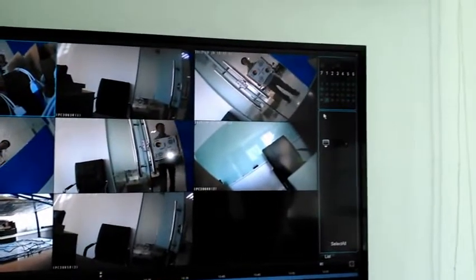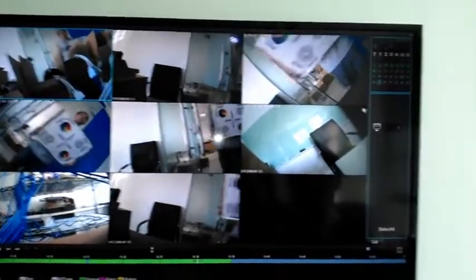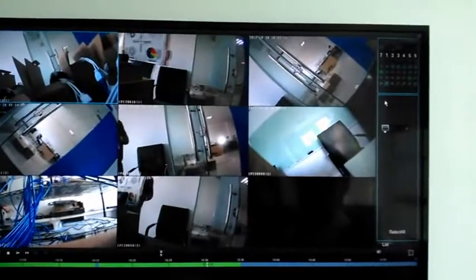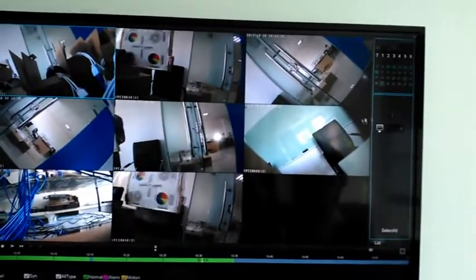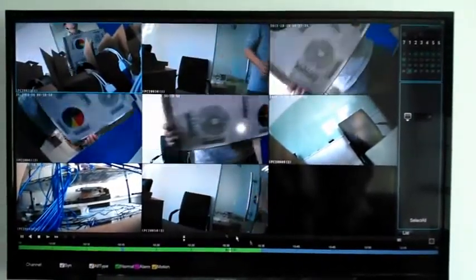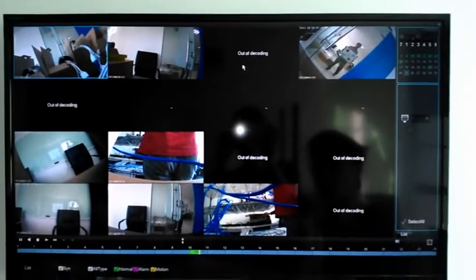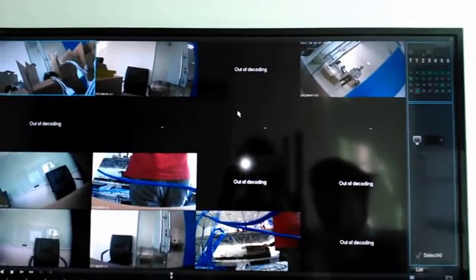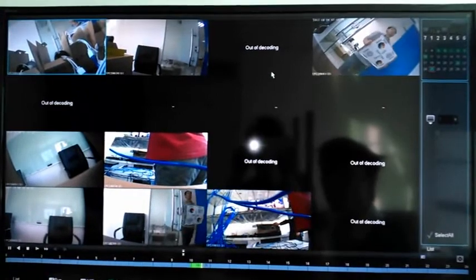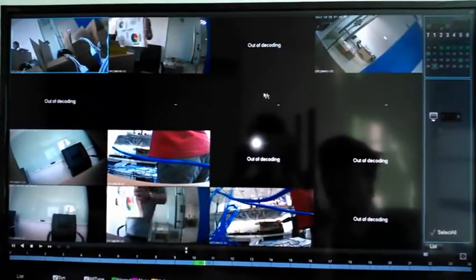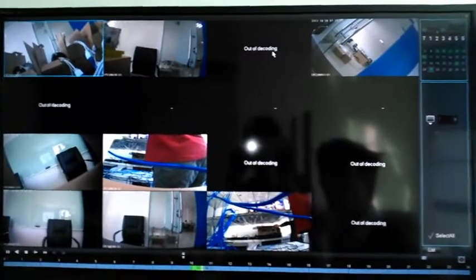If we choose 16 channels for playback, only some channels will display video, and the other channels will show no video. This is because the decoder performance cannot support that many channels simultaneously. The NVR is 16-channel 720p, so the maximum supported playback is 8 channels. If you choose 16 channels, the others will show out of decoding. This is a performance limitation, not an NVR defect.